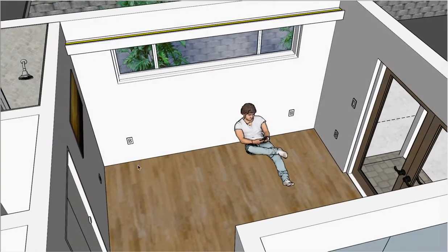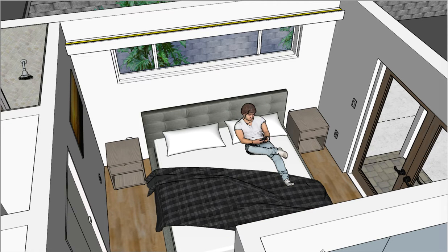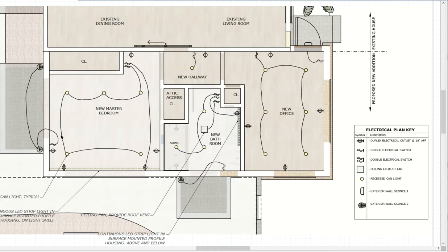So basically I have outlets located behind each of the nightstands. Oh, I just remembered what I was going to tell you. By code, we need an electrical outlet on each wall. So that explains maybe some of the locations. These are your outlets for your desks. This one in the middle of the wall over here, and this one, are required by code, so you might plug a vacuum cleaner in there, or something that needs access. Some of these seem like you don't really need them or want them, but we need them by code. So each wall needs an outlet.